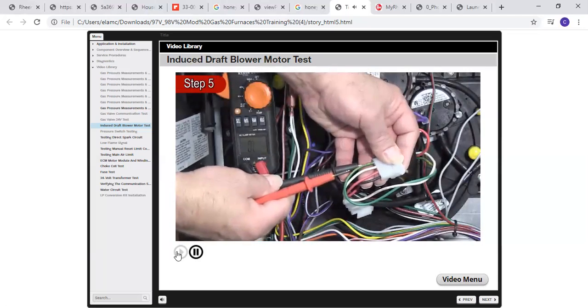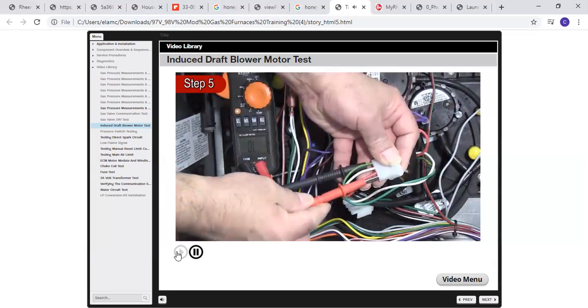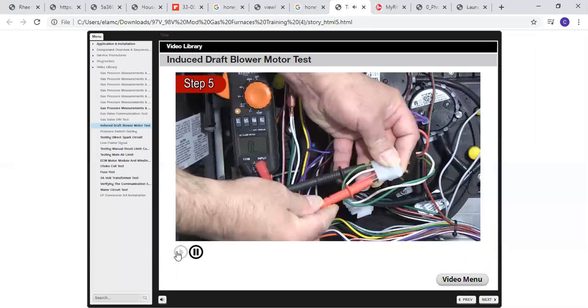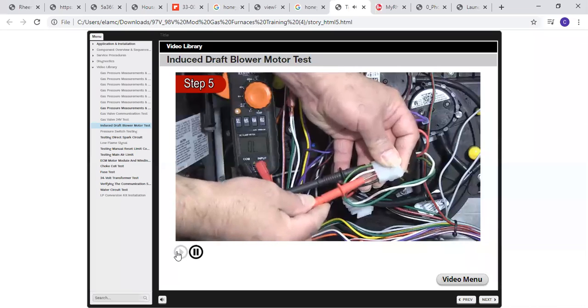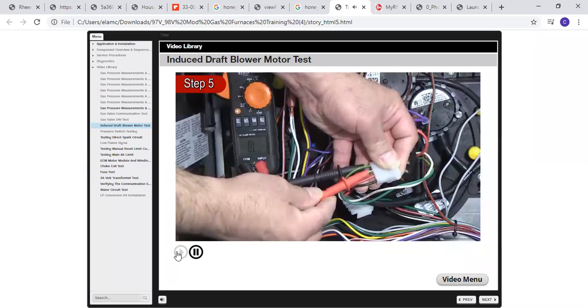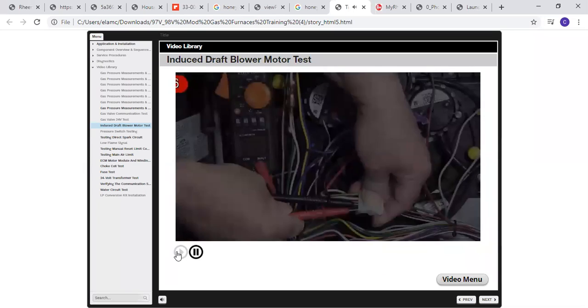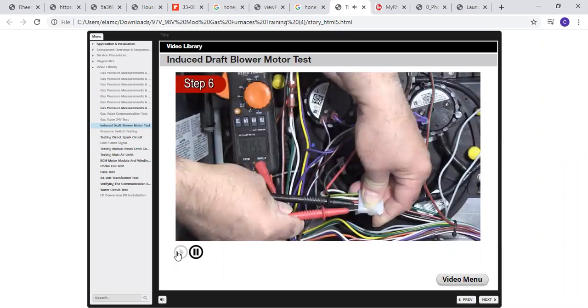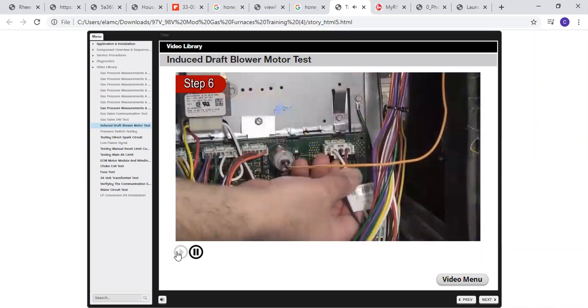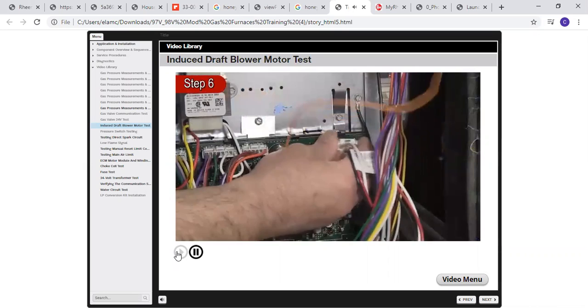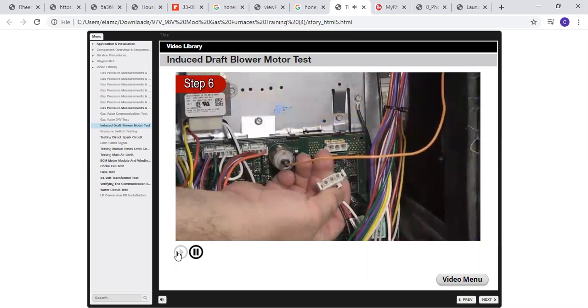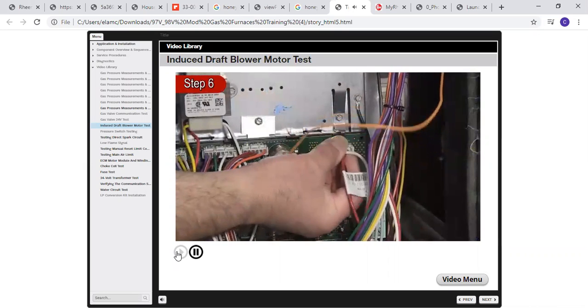Step 5. Measure the resistance from L1, L2, and L3 windings to the green ground wire. The resistance should read infinite. If resistance is measured, the induced draft blower motor is shorted to ground. Replace the motor. Step 6. If the motor checks out okay, check the wiring from the motor to the integrated furnace control. If the motor will still not run, replace the integrated furnace control.